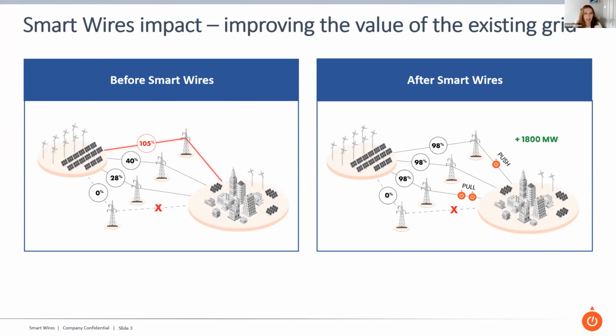It's a mesh network, usually trying to connect generators to demand. And if you think about this in the context of Ireland, you could imagine the generation in the west coast, the wind, and then all of the demand in the east coast, where Dublin is and all the data centres are, and a meshed grid in between made up of 400, 220 and 110 kV lines, all of different sizes, lengths and construction type. This grid has been built up over nearly 100 years, and one of the characteristics which is common across all grids is that the amount of power that will flow down a power line is determined by its impedance or its resistance.